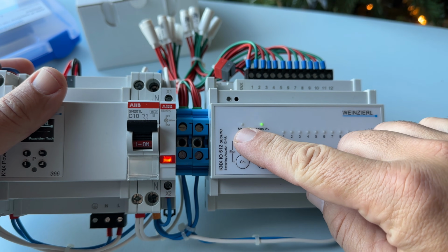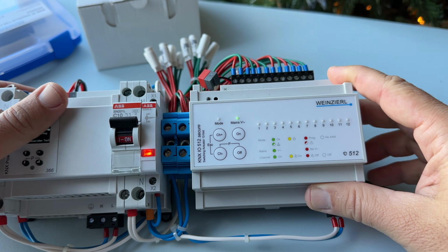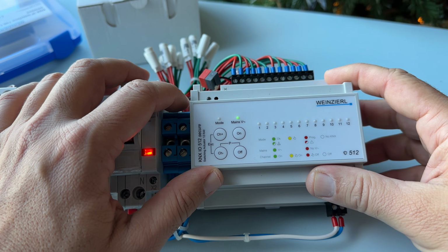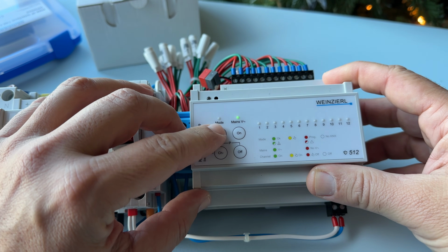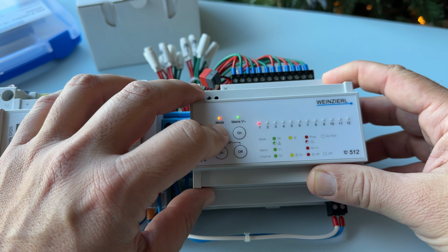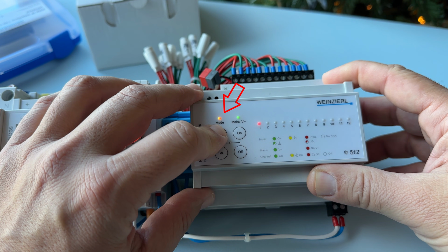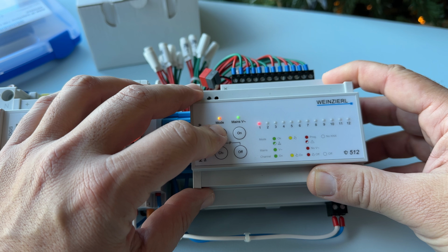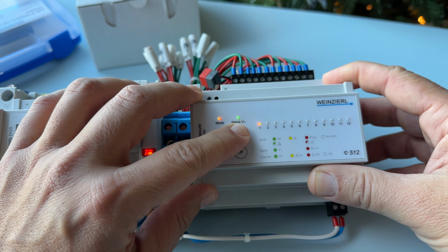Of course, right now, the mode LED switches off, indicating that there is no KNX connection. To manually control the outputs, briefly press the channel plus button. The first output is selected, and the mode LED turns orange to indicate manual mode. Then, to turn the selected output on or off, simply press the on or off button.